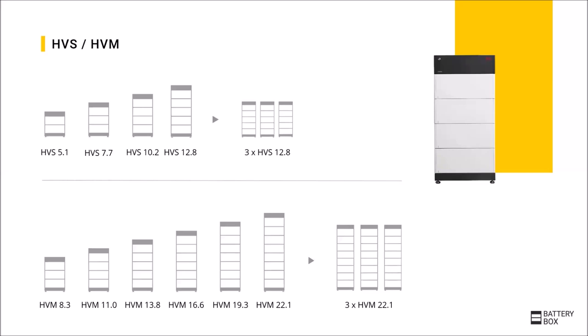With the HVM, a module has a capacity of 2.76 kilowatt hours and a voltage of 50 volts. Here you can start with three modules and a voltage of 150 volts and a capacity of 8.3 kilowatt hours. And you can choose up to eight modules, which corresponds to a voltage of around 400 volts and a capacity of 22.1 kilowatt hours.